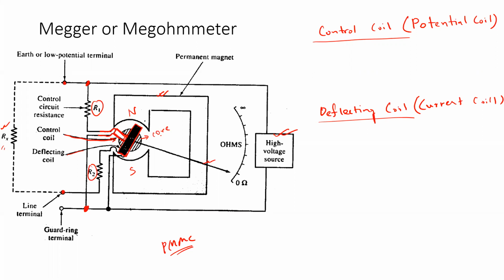Now, this is in general the construction. Apart from the two terminals where you have to connect your unknown resistance, there is another terminal provided by the meter, the guard ring terminal. The guard ring, which is available with the insulating material, has to be connected with this terminal of the meter. If I represent it in terms of the delta network that we saw a little earlier, suppose this is terminal A, this is terminal B, and this is terminal G, the guard ring. So the guard ring of that structure should be connected with this terminal.